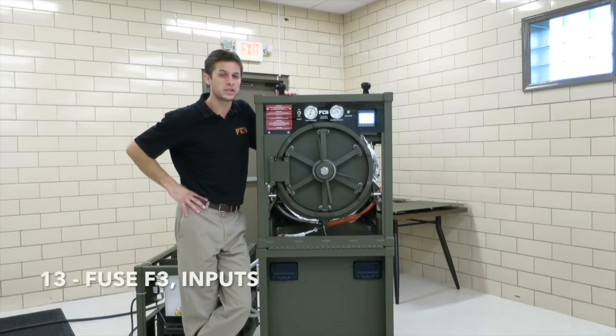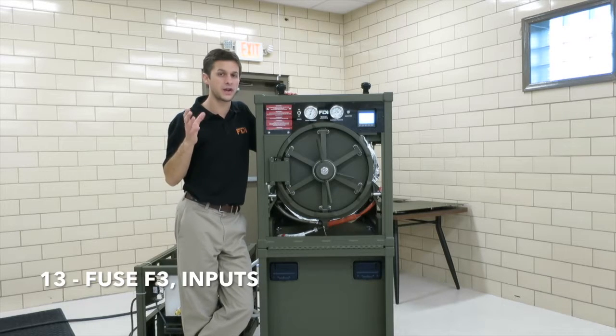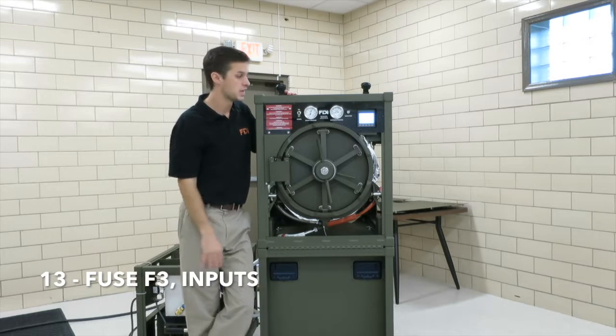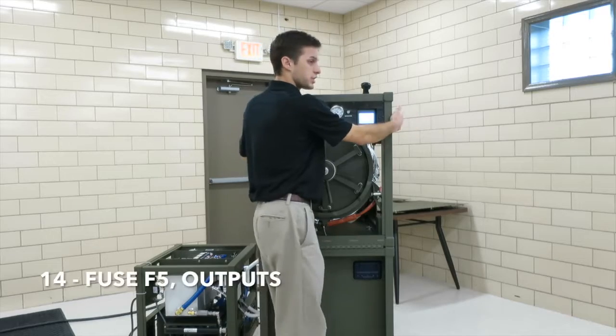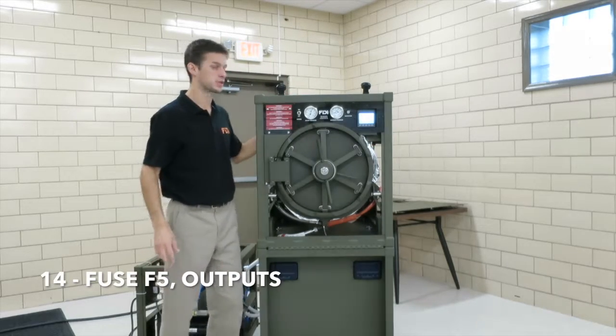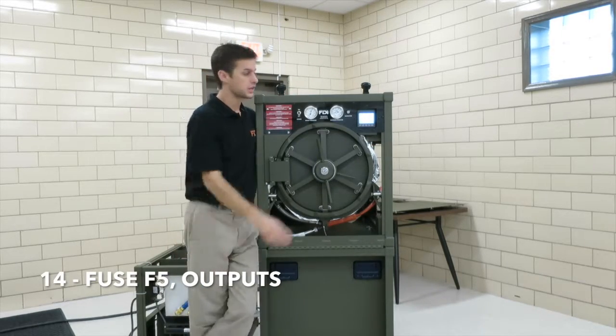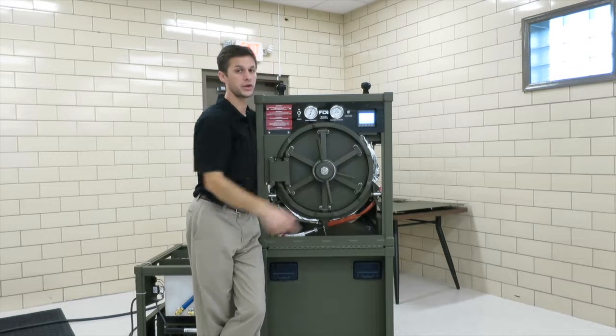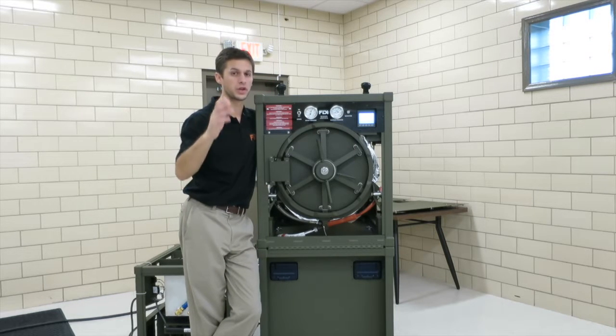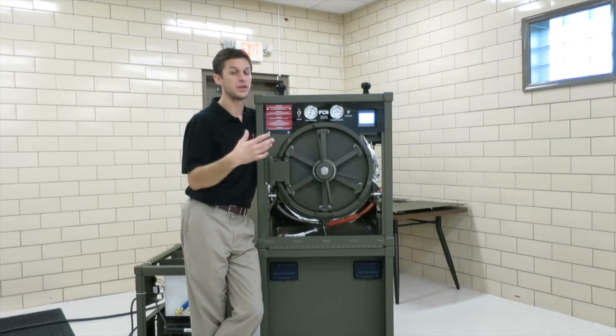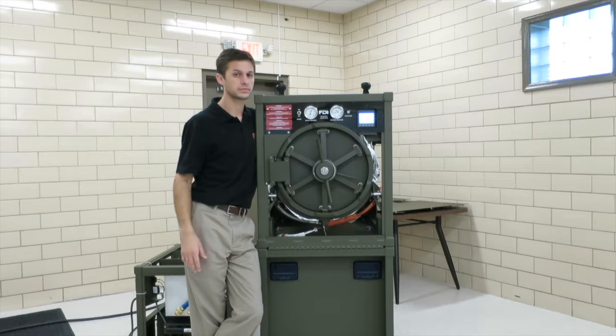Number 13 and 14 are kind of related: fuse inputs and fuse outputs. We have some fuses in the electrical enclosure to protect all the electronics. The PLC is constantly monitoring those. If those blow, you'll get one of these alarms telling you that one of those fuses is blown.